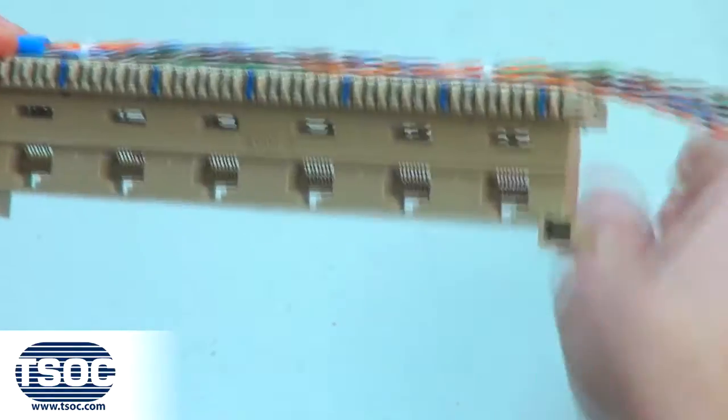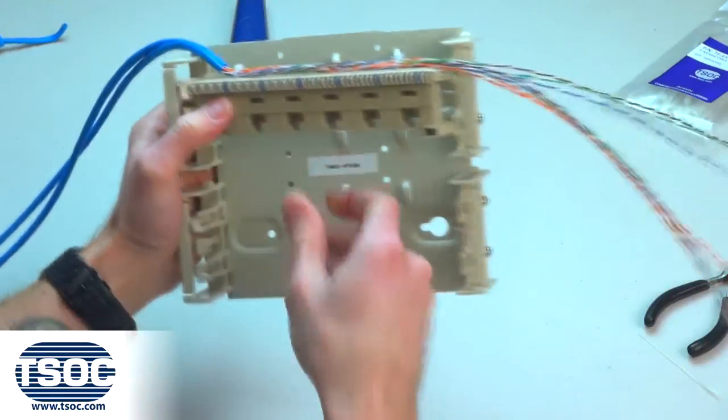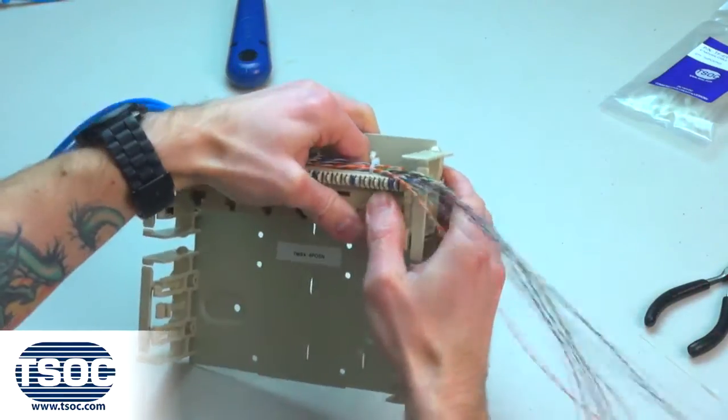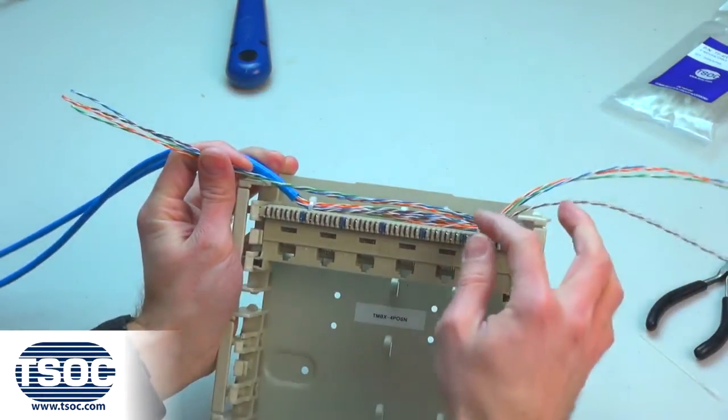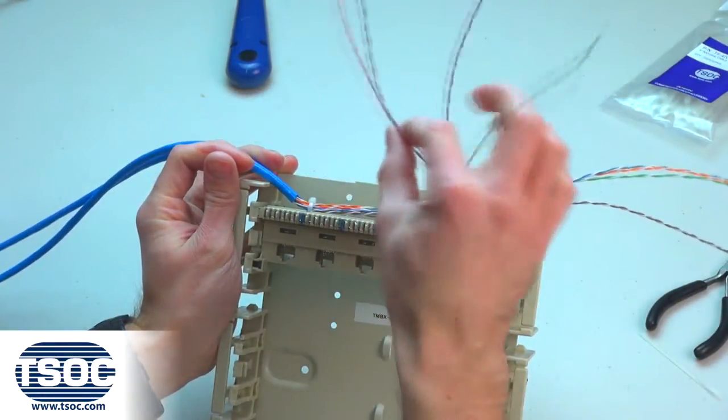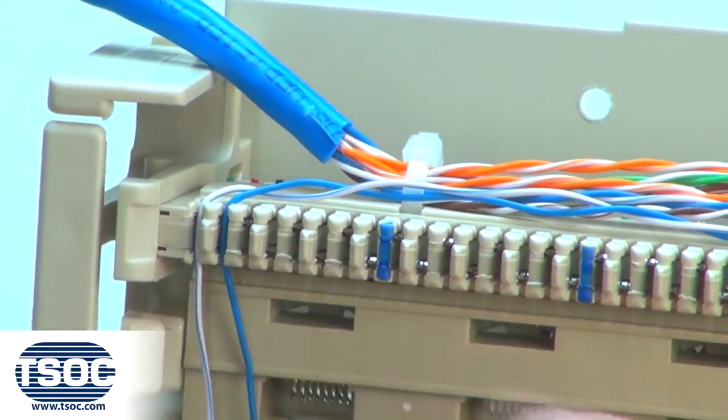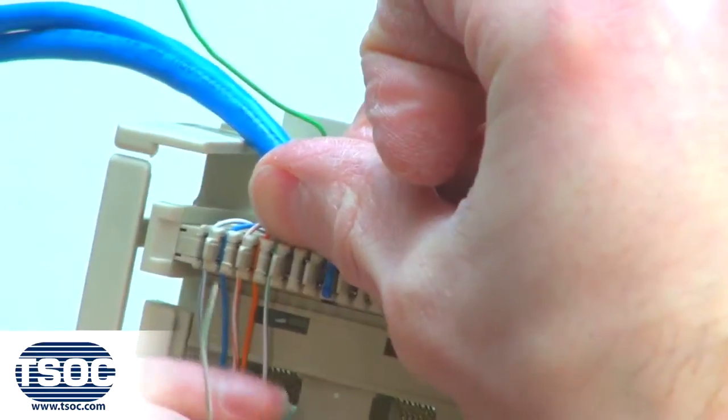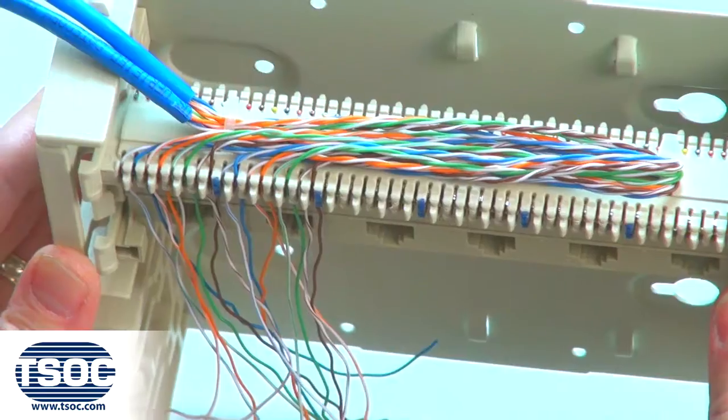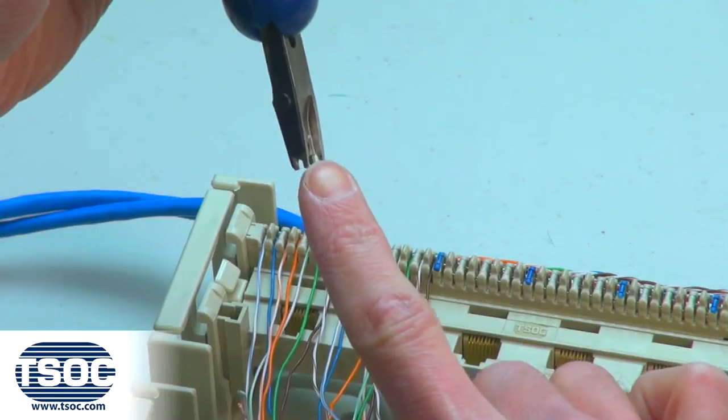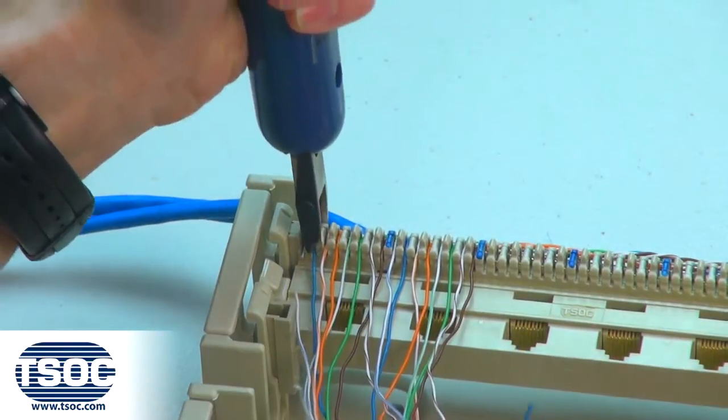Step 4: Install the distribution connector into the 100-pair distribution frame. Separate each pair of the UTP cable and lace into the modular distribution connector according to the required wiring code. Use the impact termination tool to punch down and cut one insulated conductor at a time.